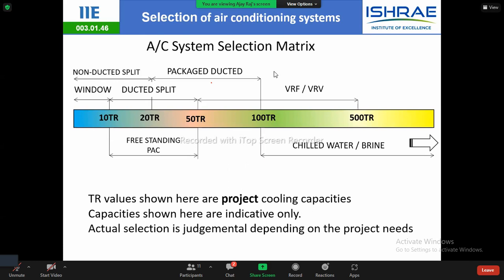Okay. Yes. So for comparison of VRV and chilled water or brine, we have considered that the efficient one is the chilled water system. If we compare VRV and the chilled water system, chilled water system we prefer above 100 TR, and from 50 TR to 100 TR we can go with the VRF and VRV system.